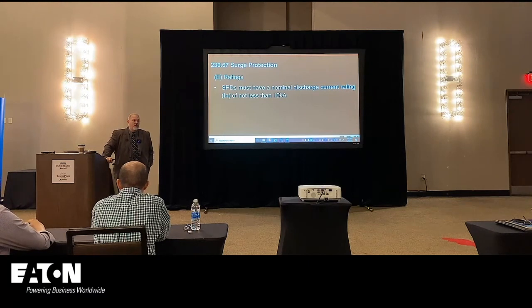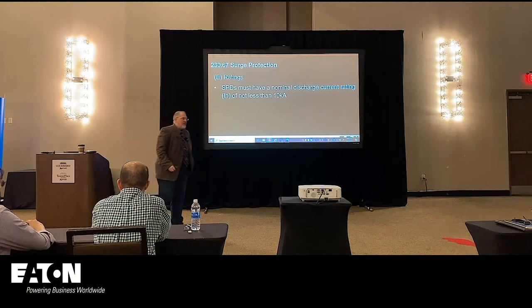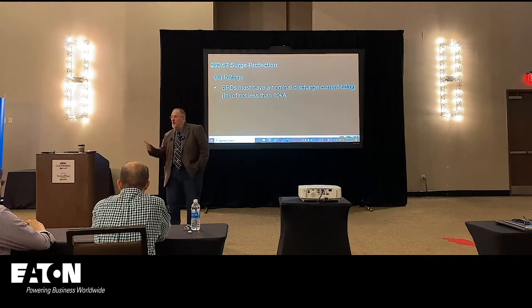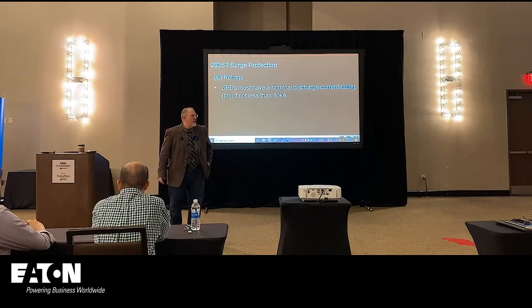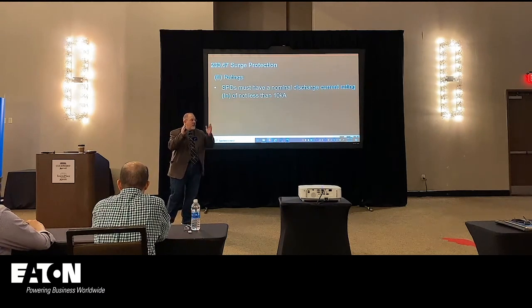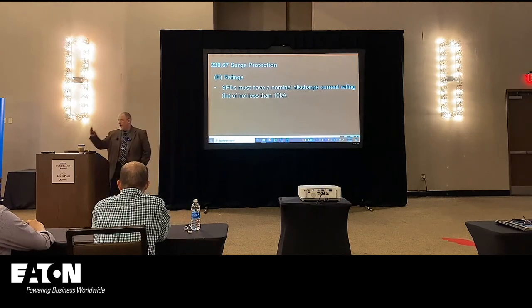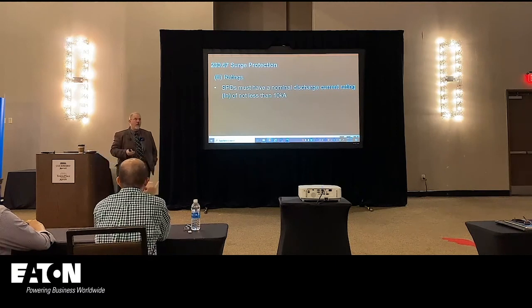controversial actually. It was appealed. There were arguments on the floor of the annual meeting. The nominal discharge current rating of not less than 10,000 amps, I liken this to the treads on a tire, or like when you're going to buy a roof, right? You're going to put shingles on the roof. You can get a 20-year shingle, a 30-year shingle, a 100-year shingle. You can put a metal roof on that lasts forever, right? So this is sort of the way they test the devices. They'll hit it with surges, and it has to survive a number of hits of certain magnitudes. So that's what this rating does, and it's more of a performance rating for longevity.